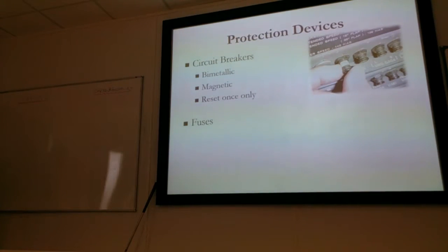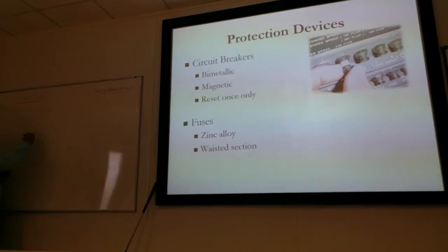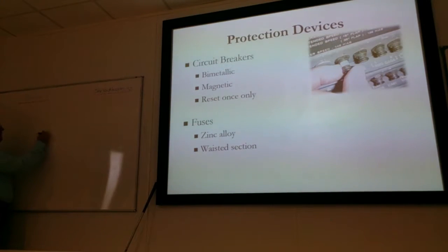The other type of protection device commonly used are fuses. Now fuses are normally a zinc alloy, and they have a waisted section in them, which is to say that what you've got is, there's your strip of zinc alloy, and all you have is a narrow section, which is the bit that's designed to fail. Because if current flowing through there, if there's too much of it, as it gets through that point, that will heat up and that will just fail through there. All seen them in our cars, I'm sure. Look at the little blade fuse, you hold it up to the light, you can see if it's popped or not, if it's blown.